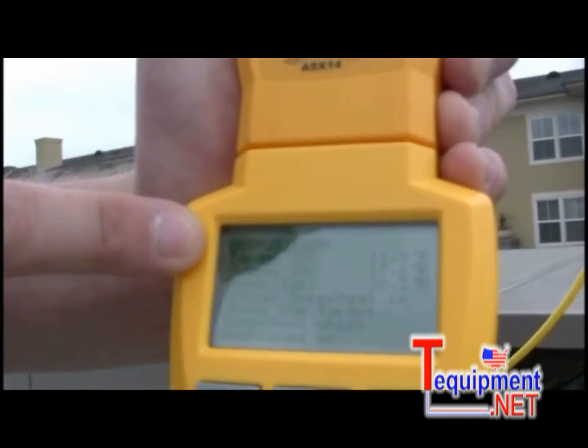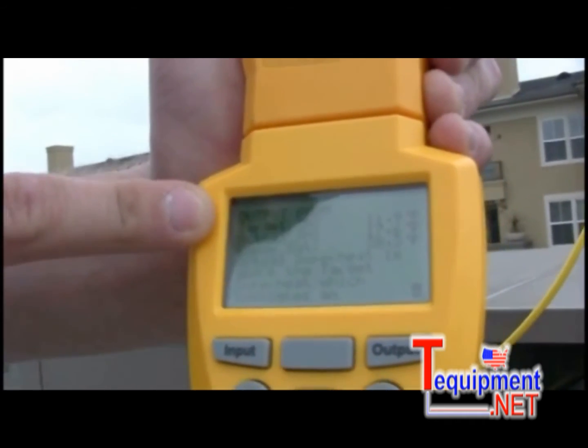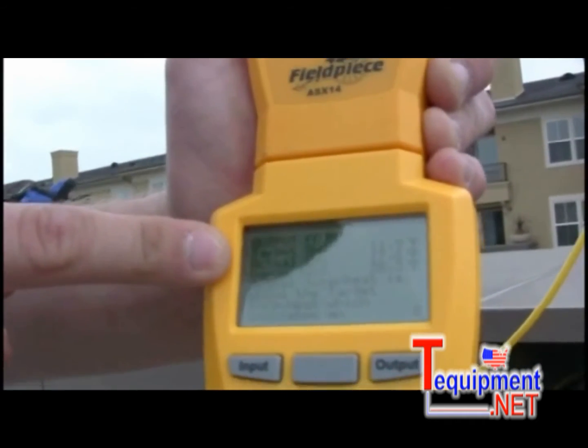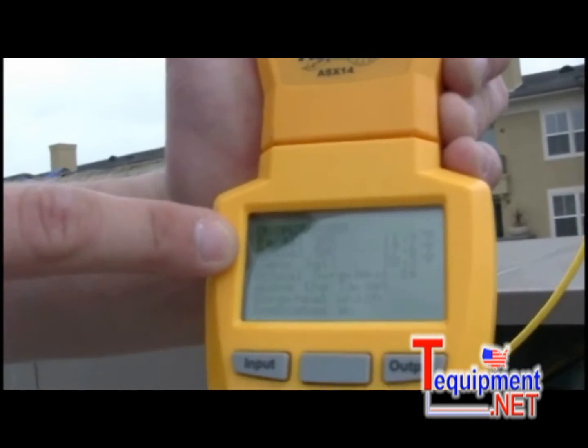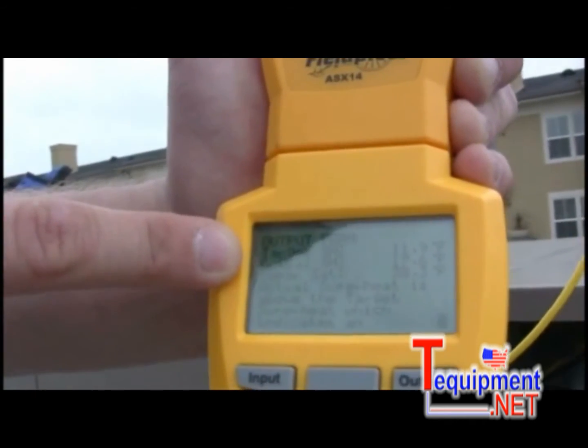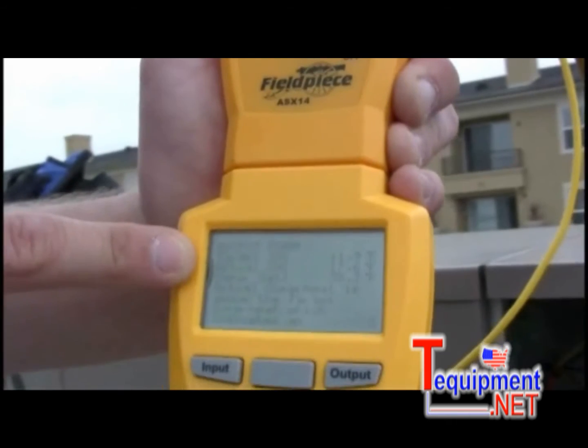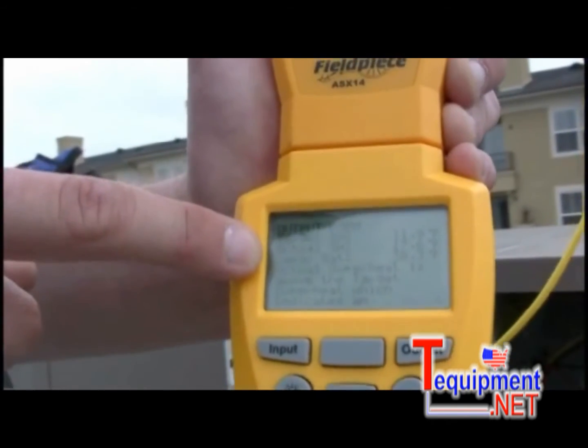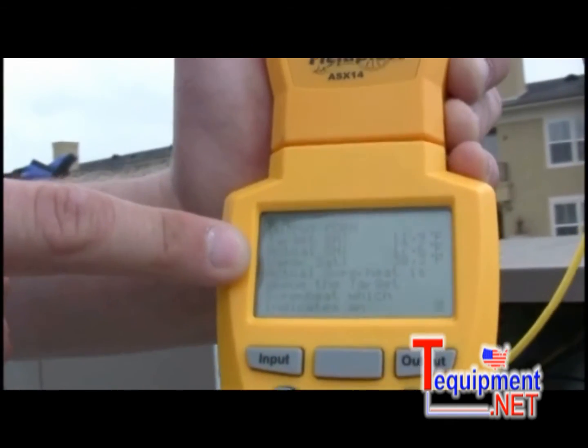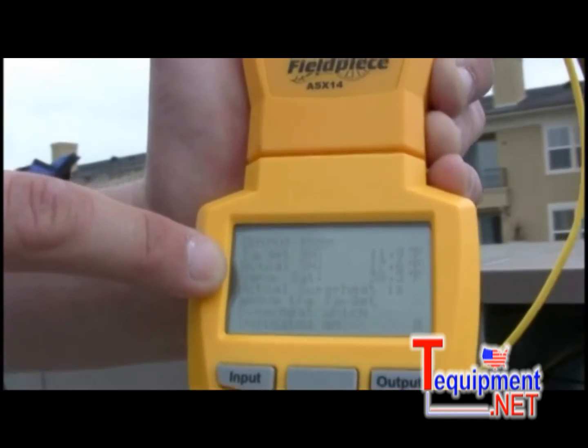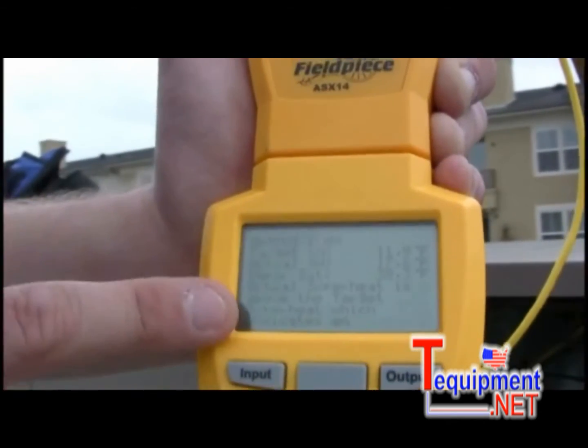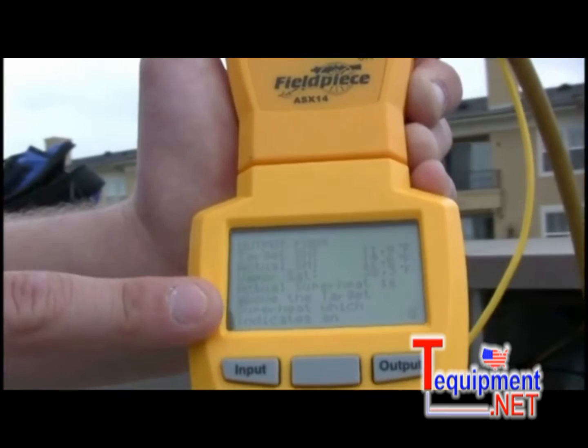So you can see here that my target superheat was 11.9. That is based off the outdoor dry bulb and the return wet bulb. And my actual superheat was 17.6, and that's based on the suction line pressure and suction line temperature. It gives us a reference number on the vapor saturation temperature, which is 38.3. Then it actually gives me an explanation of what's going on with the test.